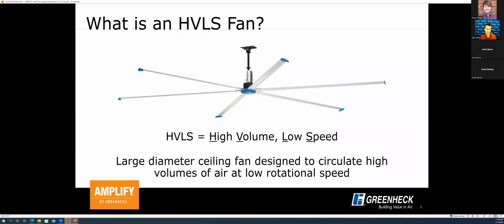To put that in perspective, when we're talking high volumes of air, you may be thinking 30, 40, 50,000 CFM, but we're actually looking at much larger volumes than that with this type of product. A 24-foot HVLS fan can move upwards of about 250,000 CFM. And for some perspective on what we mean by low speed, that same fan can move that much air at about 60 RPM, much lower operational speeds than maybe you're used to with a traditional exhaust or supply fan type of product.